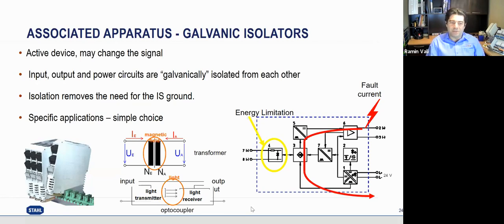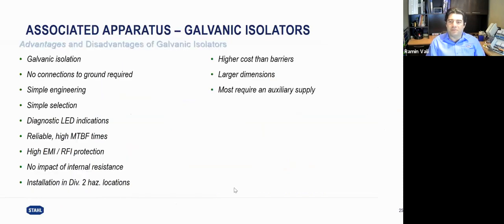Now, because of the galvanic isolation, we have some advantages here. The best thing is we don't have to ground field devices to the same ground as the safe area. This connection is not mandatory. It's simple engineering because you can choose an isolator for your application without doing a lot of calculation. So if we have an analog input, for example, to connect the transmitter in the field to the safe area PLC, we just use an isolator which is for analog input applications. Digital inputs, digital outputs, or analog outputs have their own type of isolator.